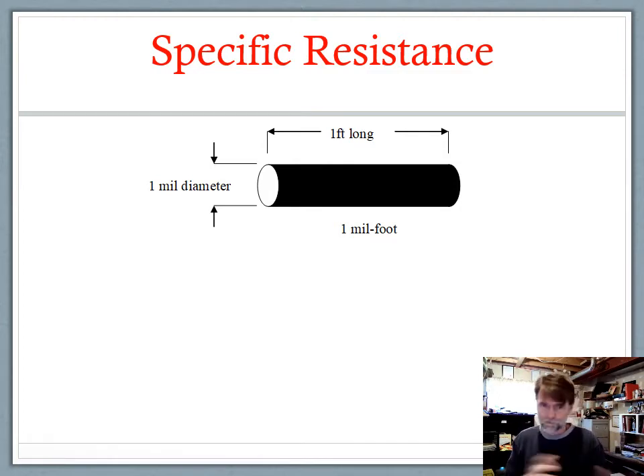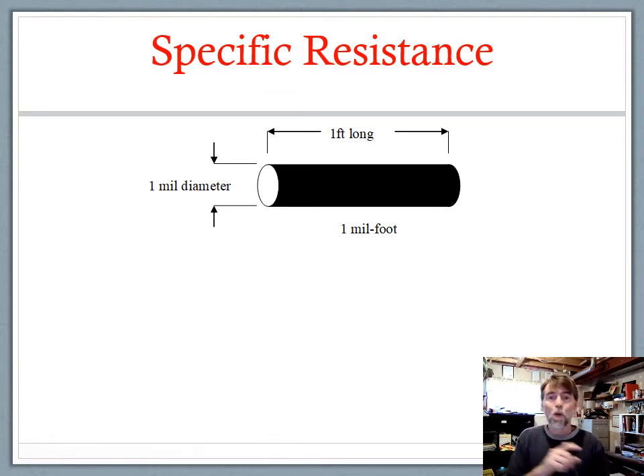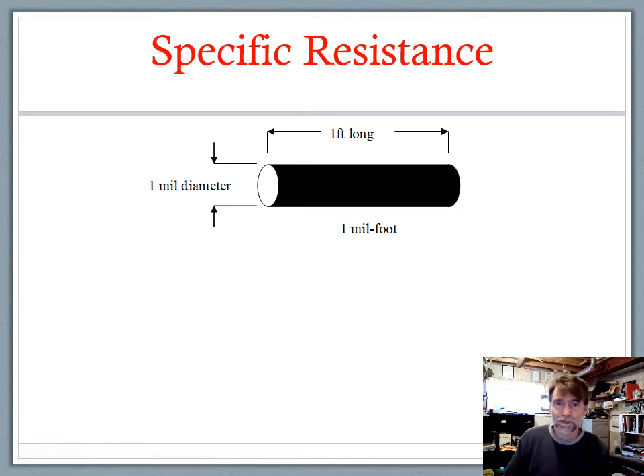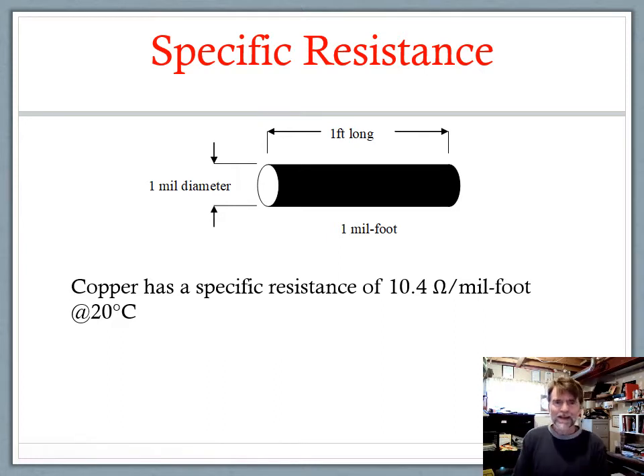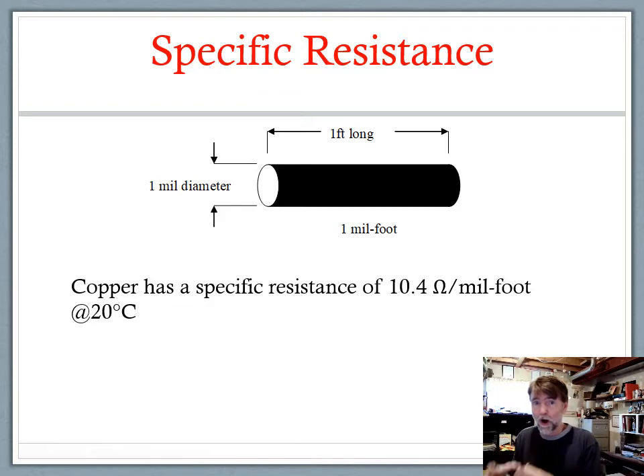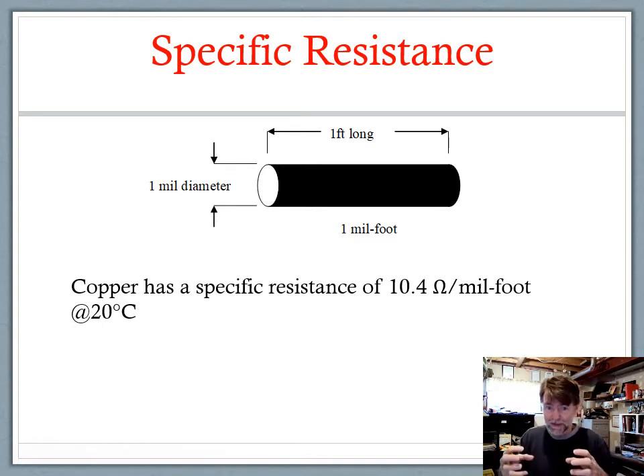Whether we talk about a diameter of one mil or a circular mil area of one circular mil, it's the same — that is the cross-sectional area of the conductor, and it's one foot long. This is an incredibly tiny conductor, but these are the conditions at which we can specify the exact resistance of the conductor so we can compare different conductors. For copper, the specific resistance is 10.4 ohms per mil foot at 20 degrees Celsius. If we control all the variables — diameter, length, and temperature — specified as one mil in diameter, one foot long at 20 degrees, the resistance that conductor offers is 10.4 ohms.